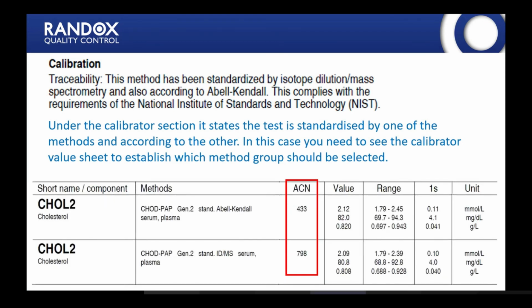Okay, so there you go. This is a different example, but something similar, with different standardizations. It's the same kit, but using two different standardizations: one using IDMS, and the other one Abell-Kendall. Same sort of situation we've just mentioned.